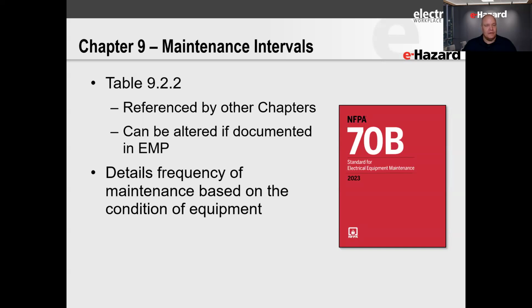It's not bad to follow 70B, but it wouldn't be inappropriate to follow the manufacturer's instructions either. I would say go with whatever is the tighter maintenance interval, and that's going to help you improve your reliability of equipment. Chapter 9 of 70B spells out these intervals, but if you have a run of good luck and go a couple cycles without noticing any issues, you're permitted to extend the intervals a bit longer between maintenance.